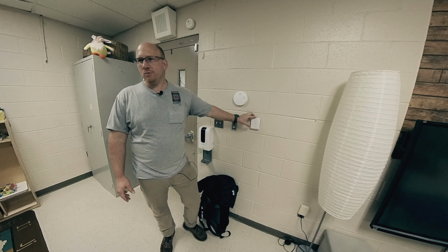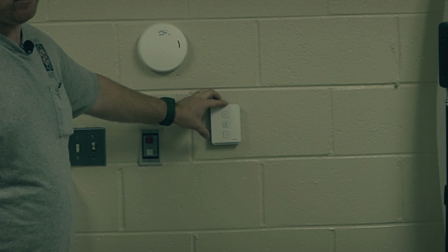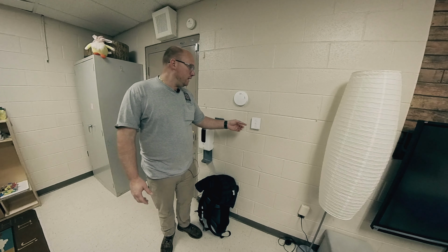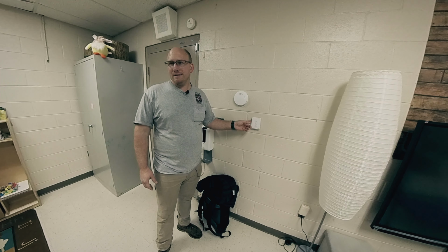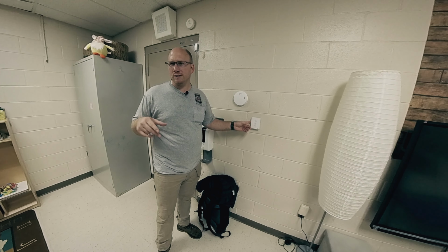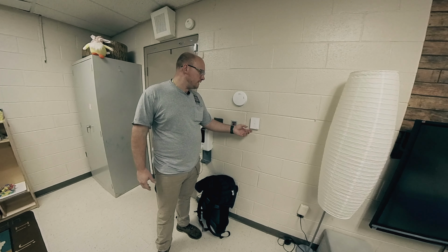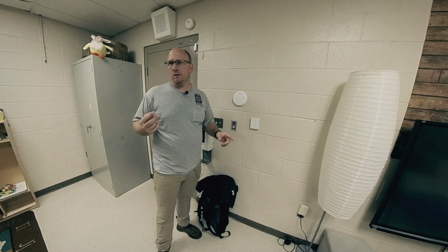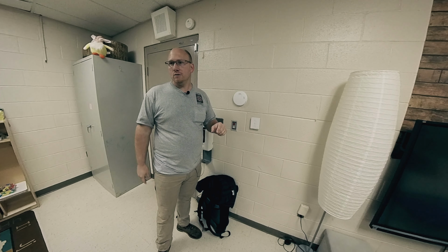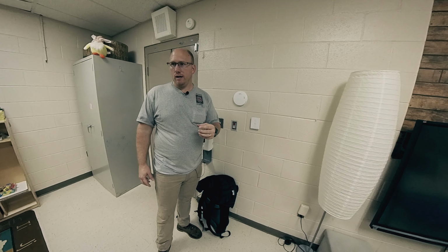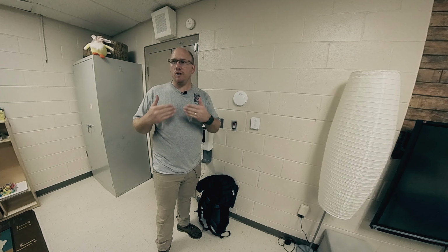Pretty basic. These thermostats are a combination of temperature, humidity, and CO2, but there's no display, so if you want to view your CO2 and humidity, you'll have to get on your computer. I think it's 2 degrees up, 2 degrees down. When you're adjusting these, they've got LED lights in the back: red on the bottom, blue on top. It'll be a light blue and then a dark blue, and going down, a light red and then a dark red. Once you hit your bottom set point, it'll flash 3 times.